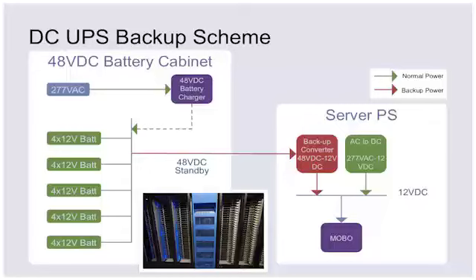So this is our DC UPS. We trickle charge our DC UPS from the 277 volt. The power supply on the server has two inputs, one for 277 and the other for 48 volt DC. In the event we lose power on the electrical distribution scheme at 277, it automatically flips over to 12 volt to sustain the server operation while the generator is spinning up.